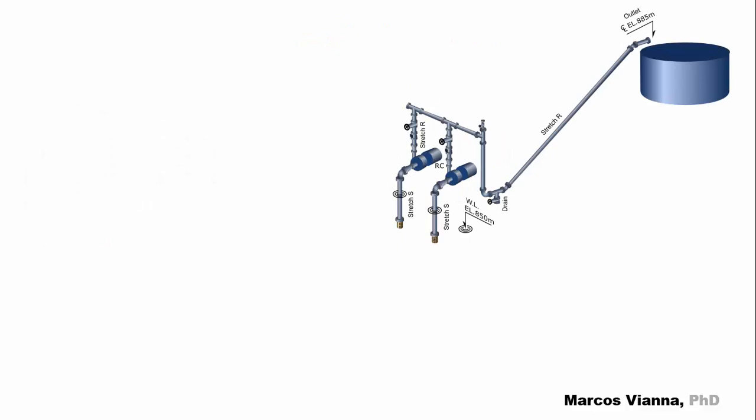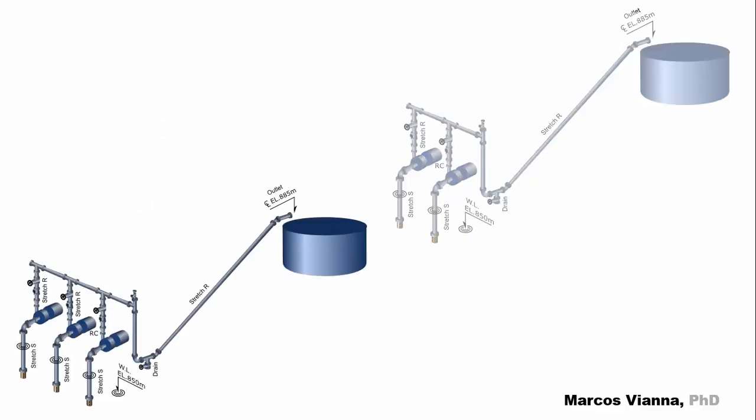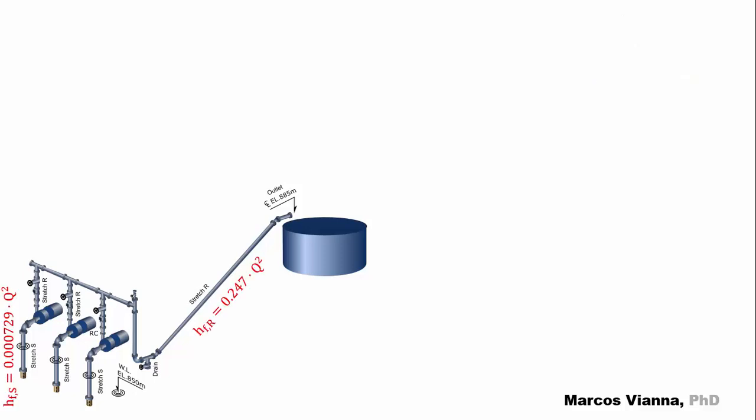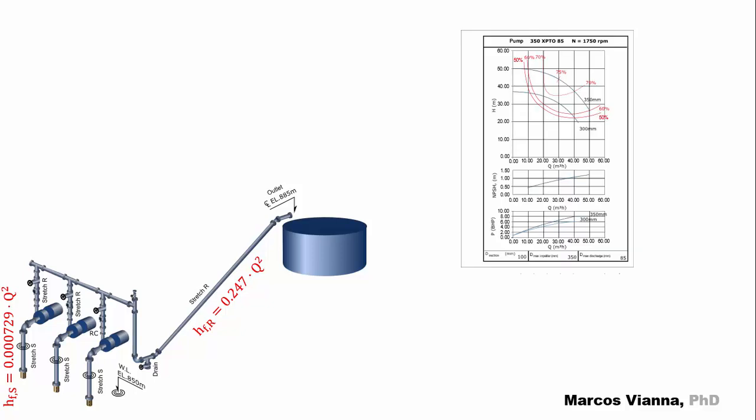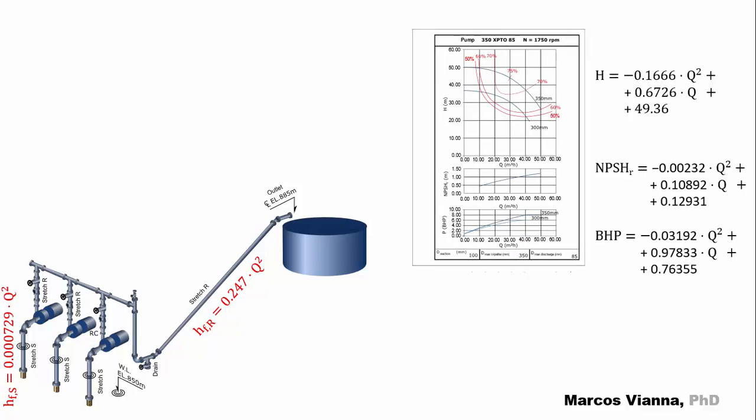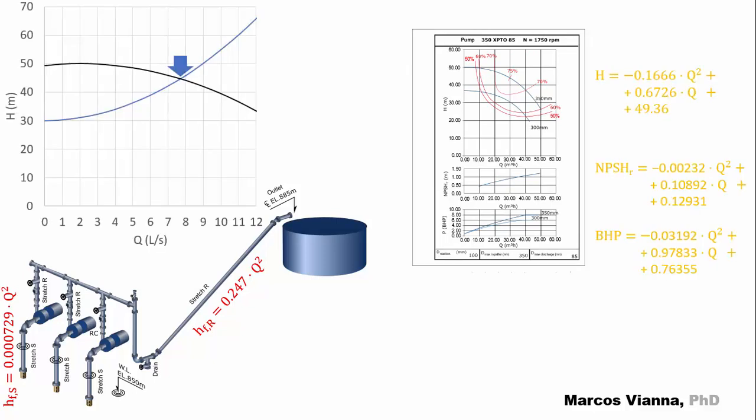But that's what happens when one pump runs alone. Let's see what happens when there's another pump in parallel at the installation. Notice that a third one is installed for standby. Again, we know these equations. And of course, we have the pump chart and equations for the head, required NPSH and BHP. Here are the characteristic curves of one pump and the system. The crossing point is the operating point.